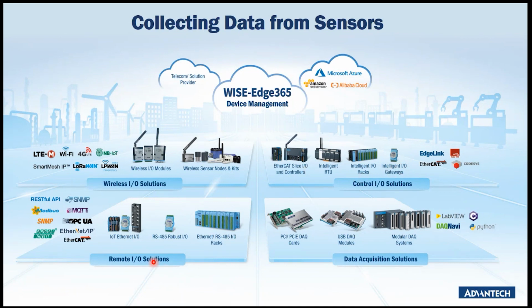After that, let's say you have simple monitoring but want to use a wired base, so we have that as well. We have RS485, which is serial based. We have Ethernet based with a lot of I/O. And also we have some niche I/O, for example for train applications. The advantage of using wired is it can support multiple types of industrial protocols such as RESTful API, SNMP, Profinet, Ethernet IP, OPC-UA, Modbus, and so on.